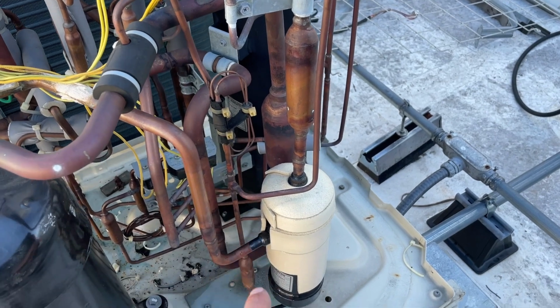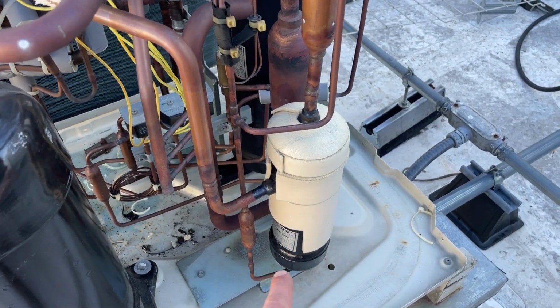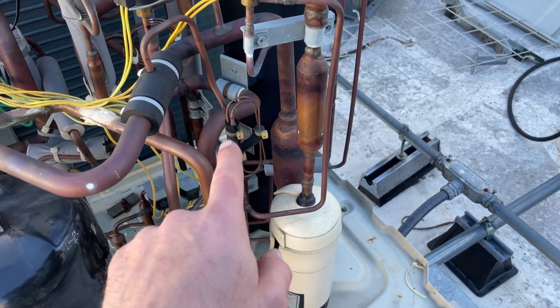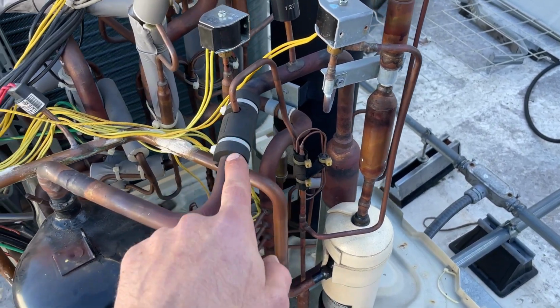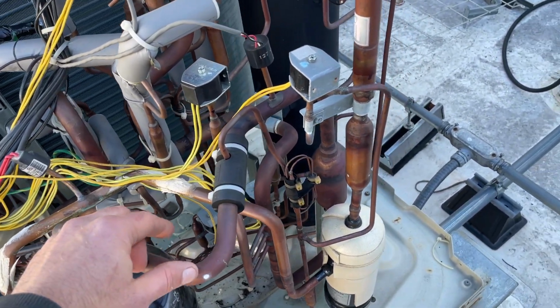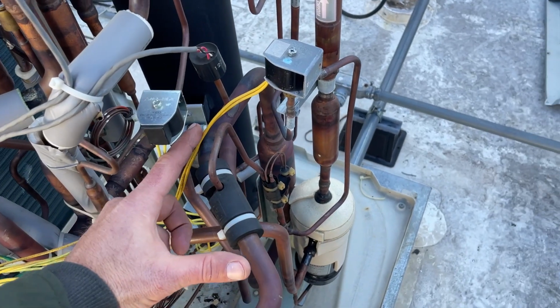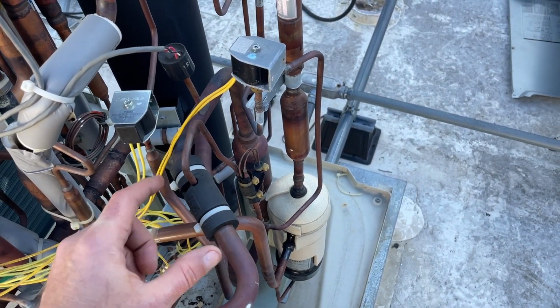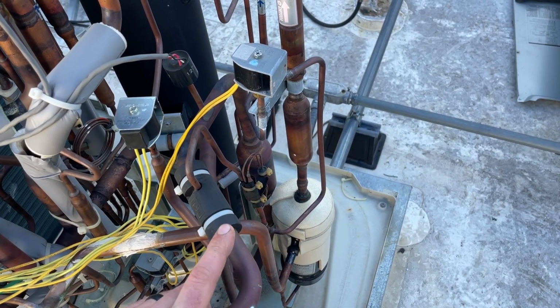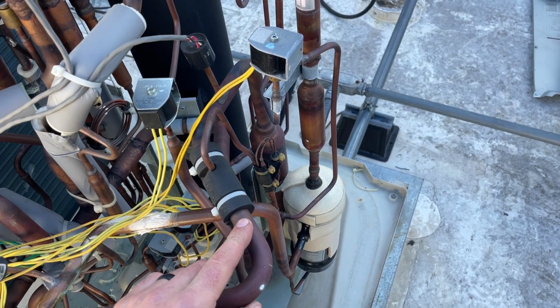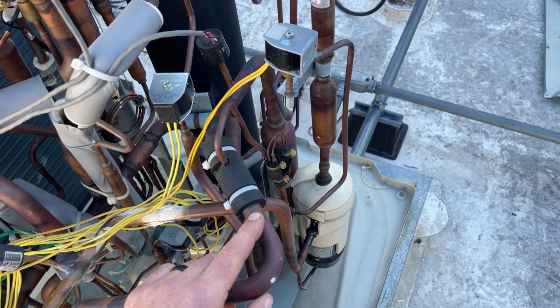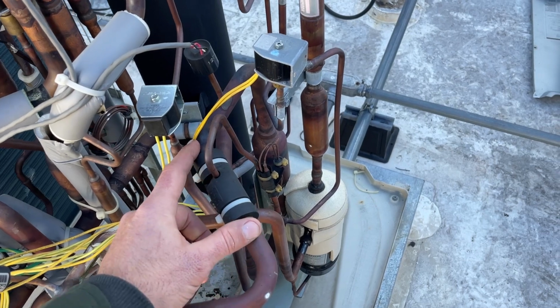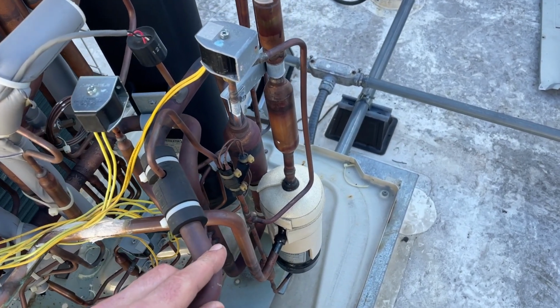The way that you check these - we're going to have oil coming up in here and constantly dripping into the suction line - is that you're going to end up with a temperature difference upstream versus downstream. So you're going to be warmer down here, and I've found somewhere between 5 to 15 degrees is what you can expect.